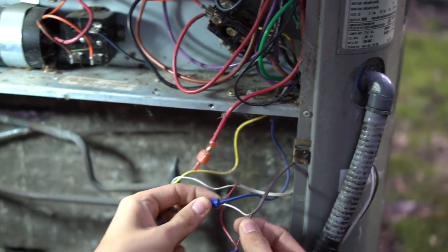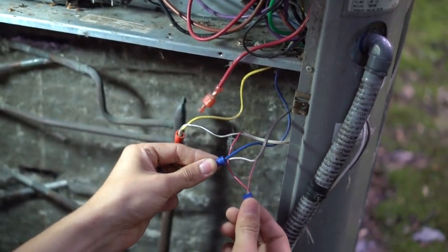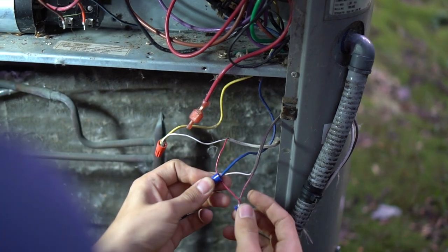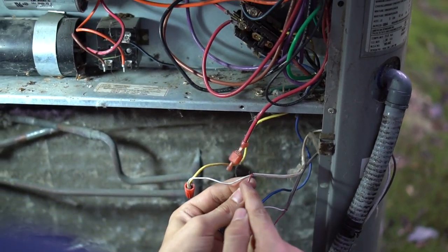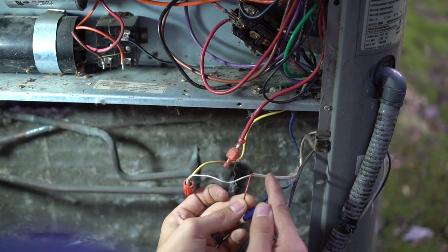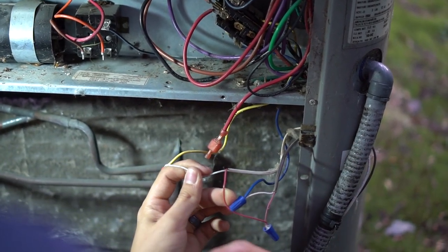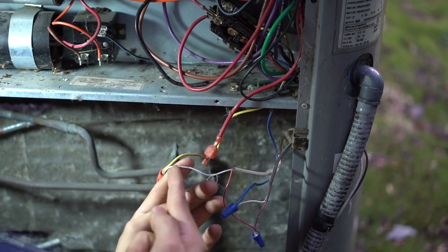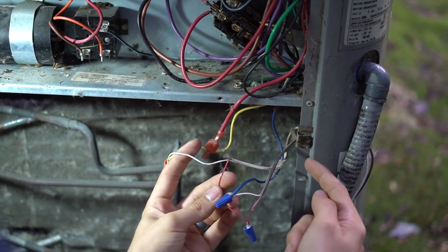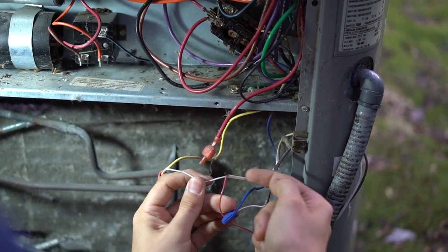That's going to be this white wire right here. But if you notice, the other wire, the red one, goes into a wire nut, and it's wire-nutted together into the red wire that comes into the white thermostat wire, which is going to my power saver switch. So it goes to the power saver switch, it goes through that switch, and it comes back on this white wire. So sometimes what happens is voltage will go into the switch, but it'll not come back out.